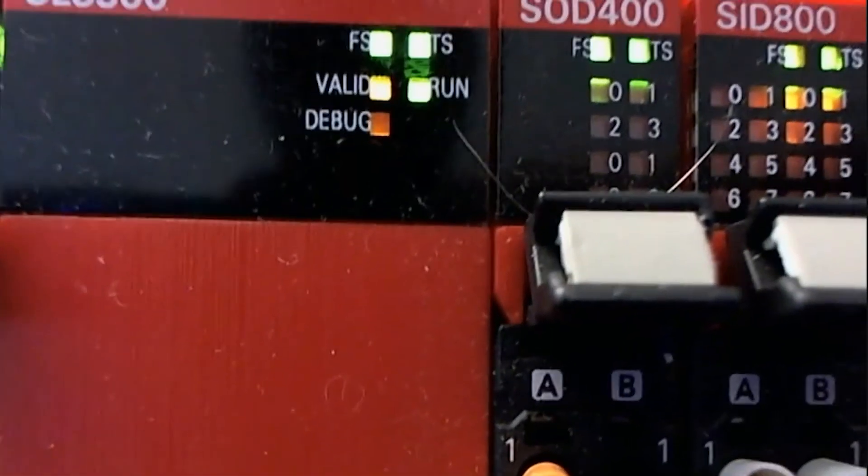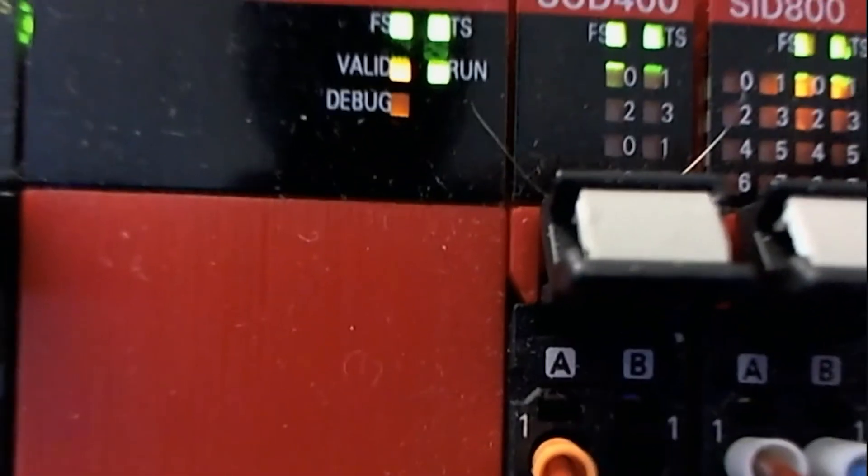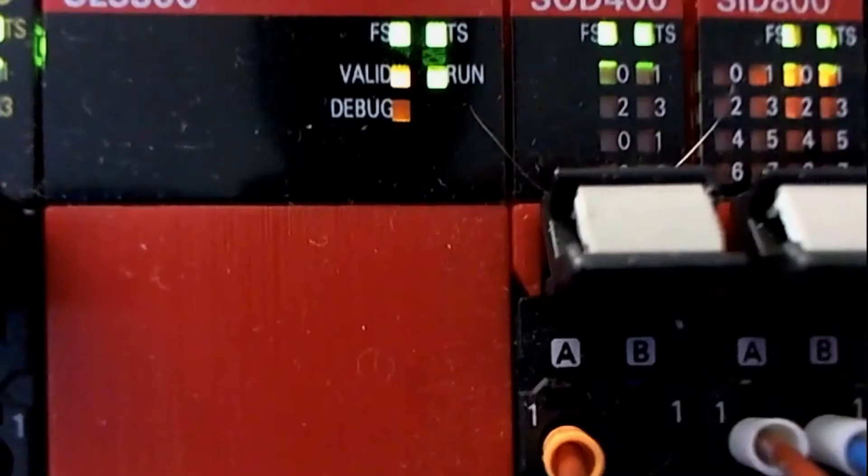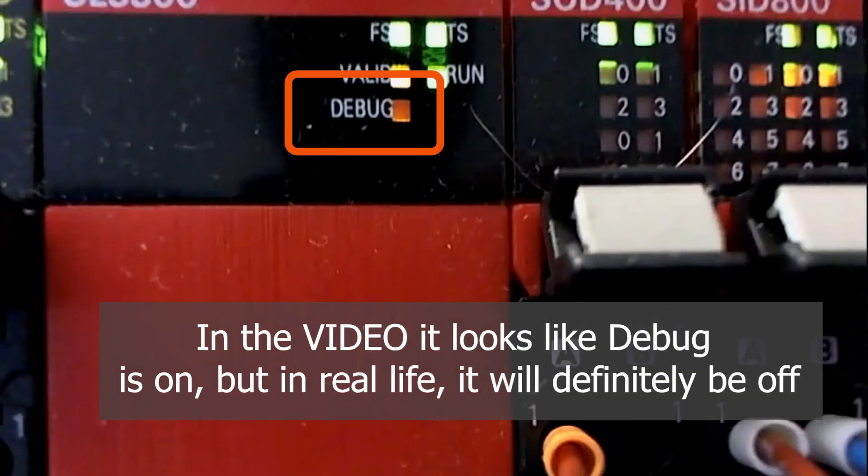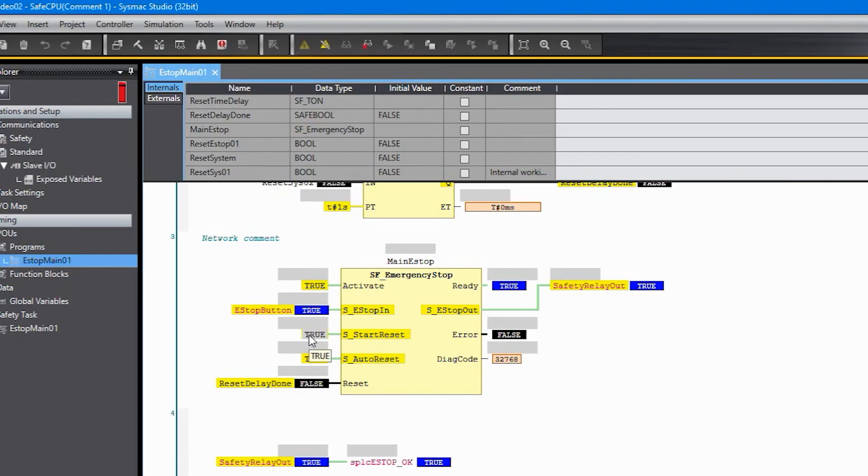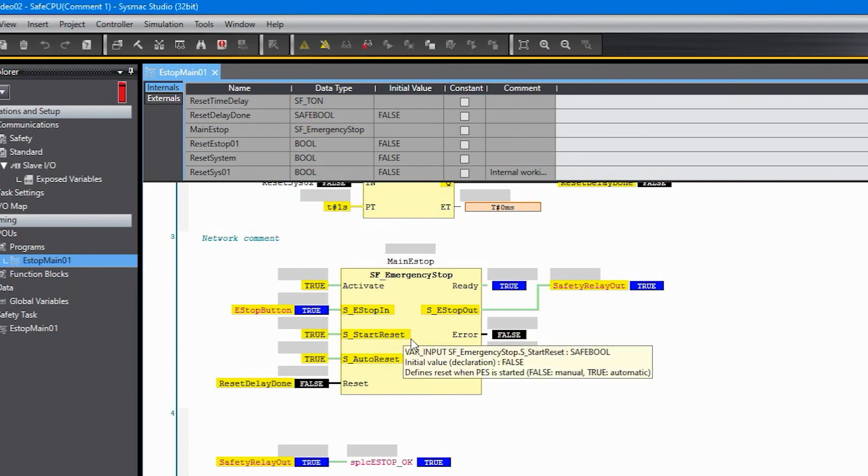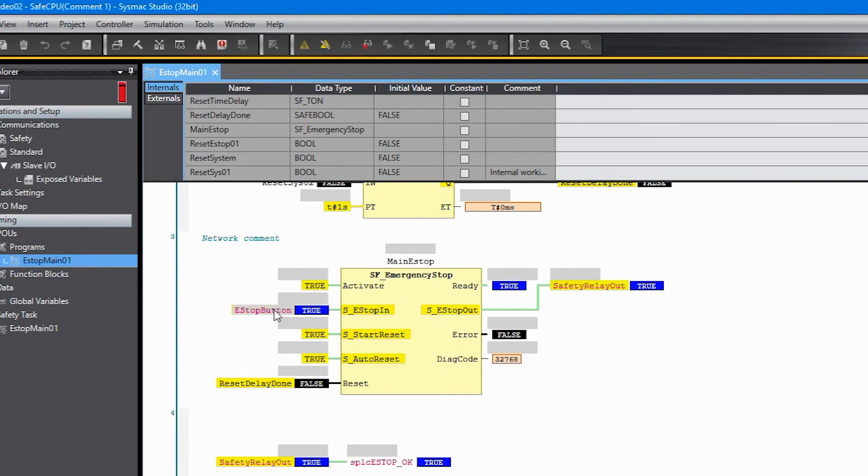And if we go back to the CPU with a little bit of blur from the photography you can see that the validation light is on and the run light is on. But the debug light even though it looks like it's on, it's off. So we're in run mode. And like I said in the very beginning with both of these set to true it's basically going to reset this safety output every time the safety input is true.